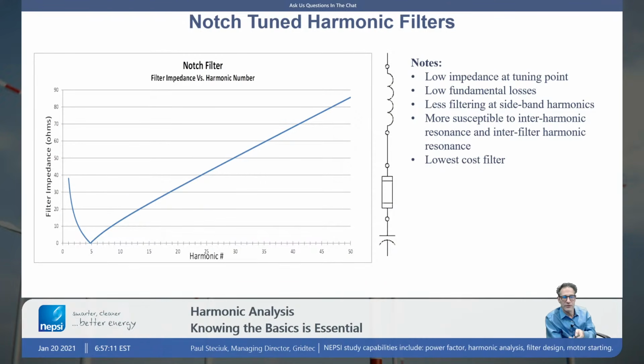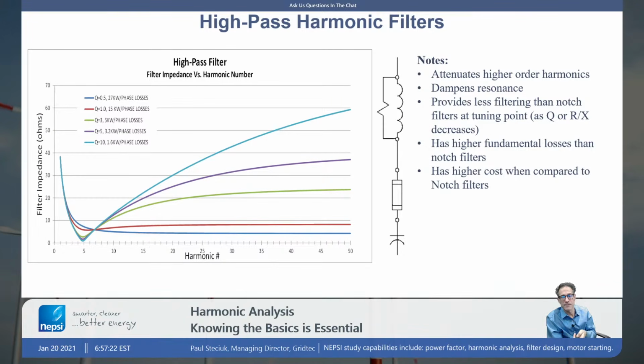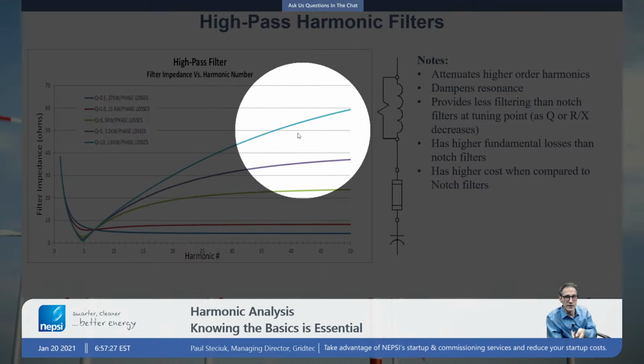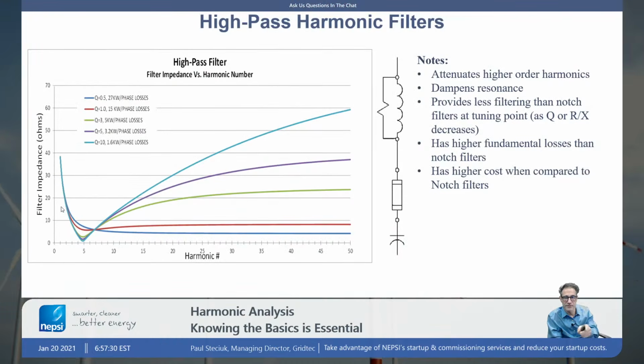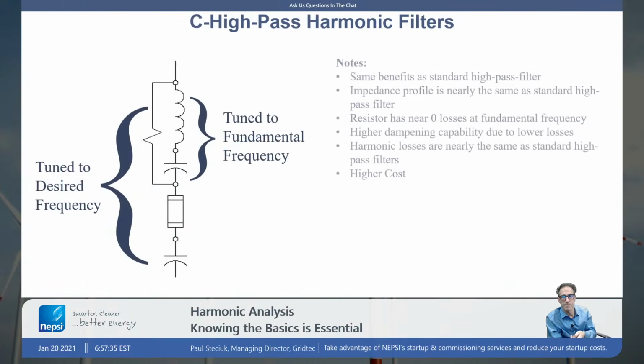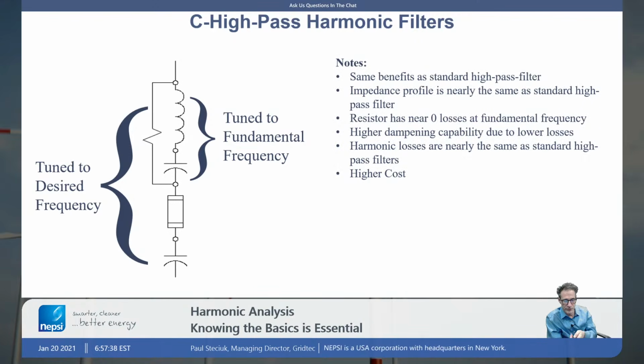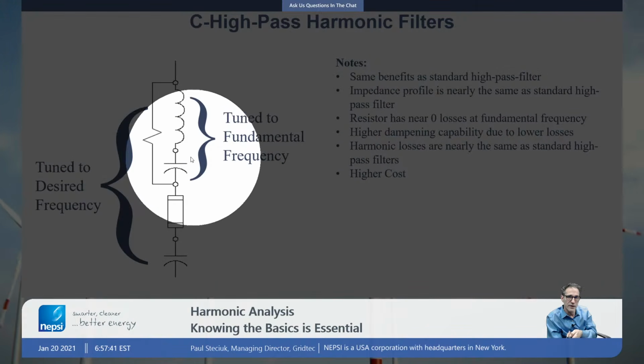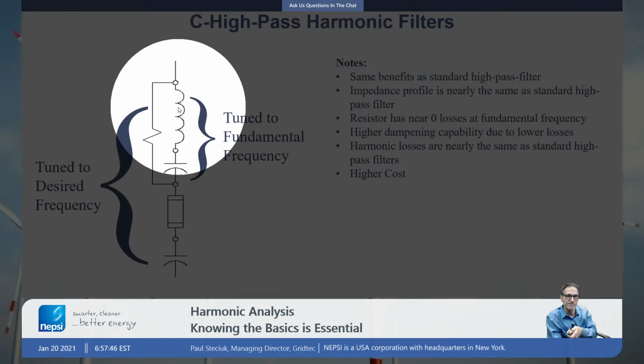So three types of filters commonly used in this system are notch tuned filters, just a reactor in series with a capacitor. We have high pass filters, and what we did was take that same notch filter, we put a resistor across it, and we can change the characteristics of the impedance of the filter, and we can dampen out those resonances that I showed on the previous slide. And then we have what's called C-high pass filters. And in this system, we're adding a second capacitor to the network. That second capacitor, in addition to this reactor, is tuned to the fundamental frequency.